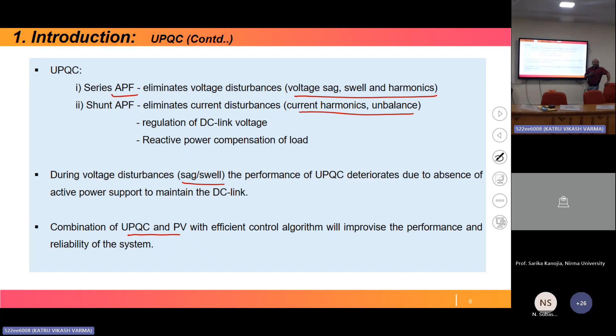When both series and shunt active power filters are there in a system, we call it UPQC, Unified Power Quality Conditioner. Now we'll see the structure, how UPQC works and how both converters of the APF are connected. During voltage disturbance, for example sag or swell, the performance of UPQC deteriorates because of the absence of active power support to maintain the DC link. What does that mean? When sag or swell is there, support is required to compensate it. If that extra support is not available, its performance will deteriorate. So who will give that extra support? For that you have to integrate PV with the UPQC. The combination of UPQC and PV with an efficient control algorithm will improve the performance when sag, swell, and all these things are there.